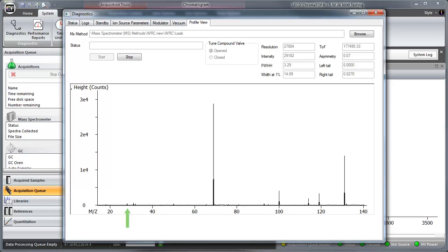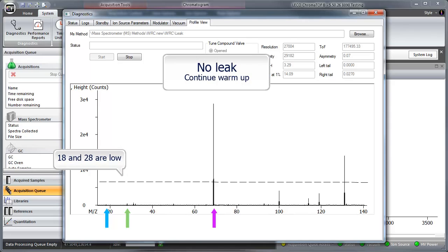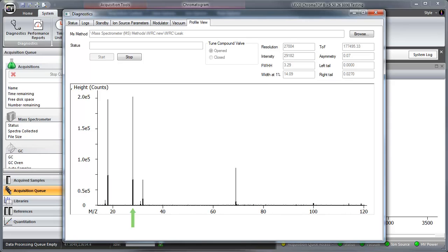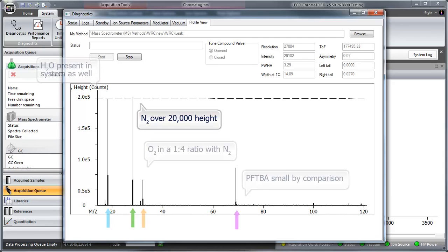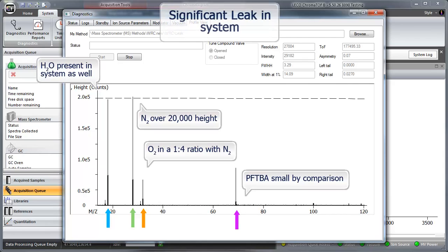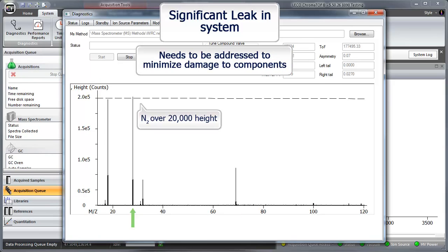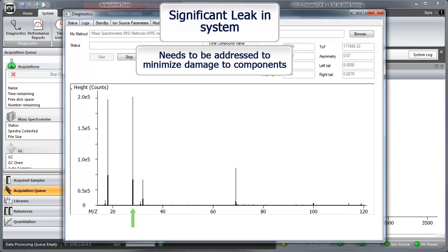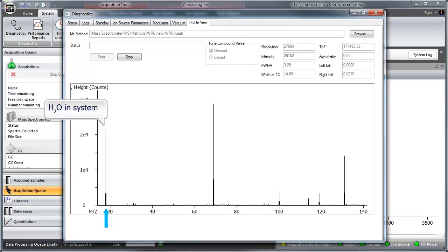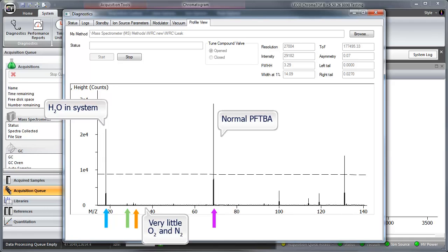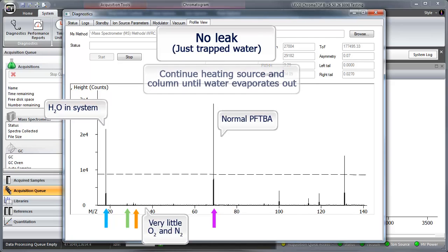If mass to charge 28 and 18 are both below 20% of mass to charge 69, then proceed with the warm-up procedure. If mass to charge 28 is greater than 20,000 height counts, as shown here, a significant leak is present and must be fixed prior to continuing. Failure to fix this leak may result in premature damage to the filament, detector, and possible contamination of the ion source. If mass to charge 18 by itself is above 20% of mass to charge 69, it is unlikely a leak exists, and in this case, continual heating of the source and column should drive the water out of the system over time.